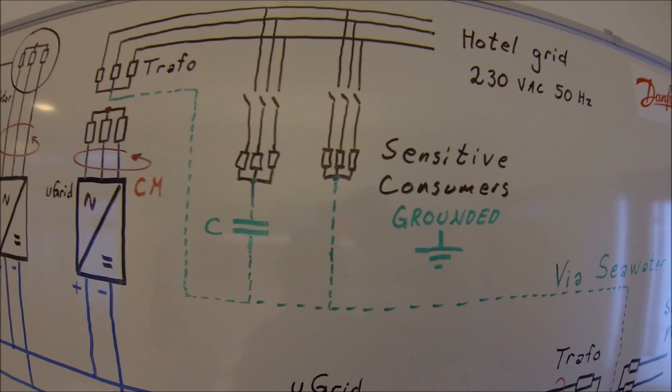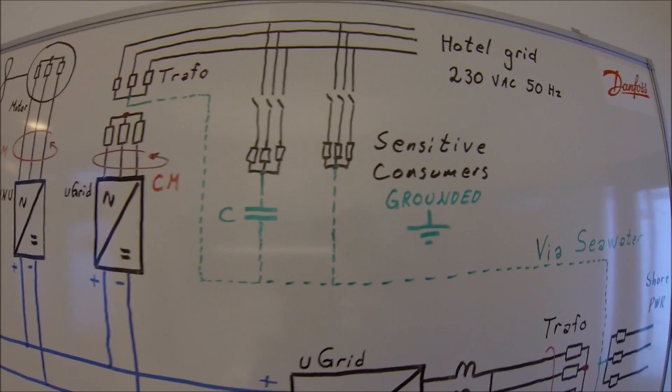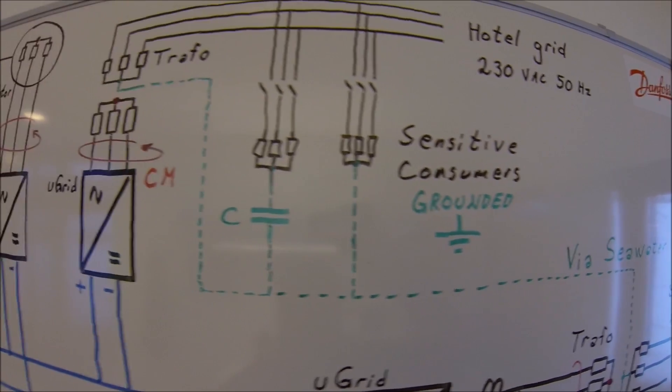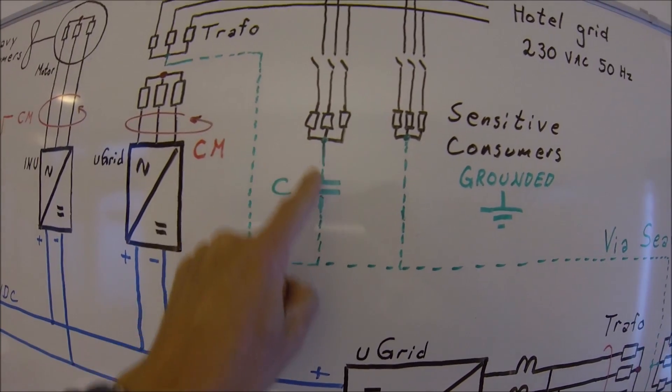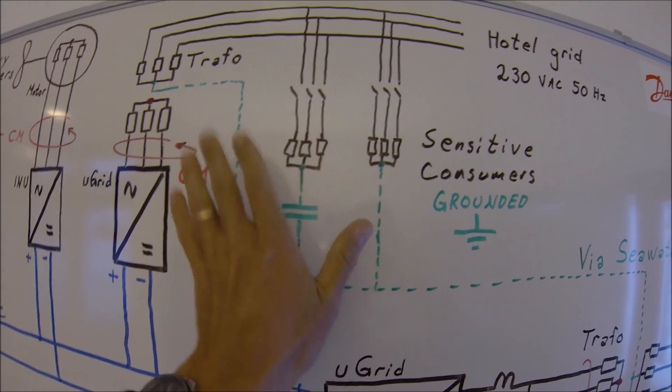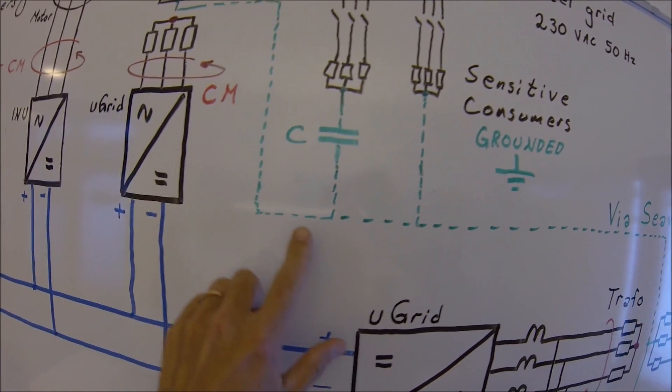If you look at the sensitive consumers like on the bridge, on the galley, your microwave ovens and all the dimmers and stuff, there are capacitive connections between these consumers and protective earth.